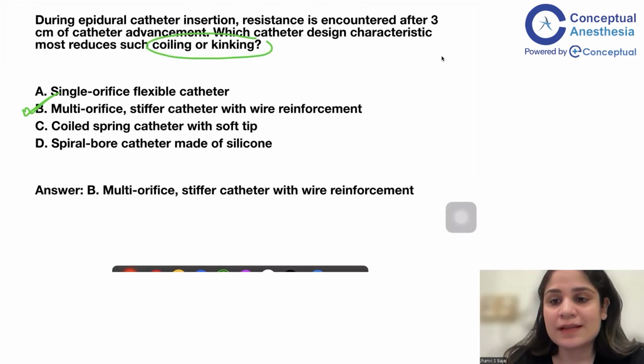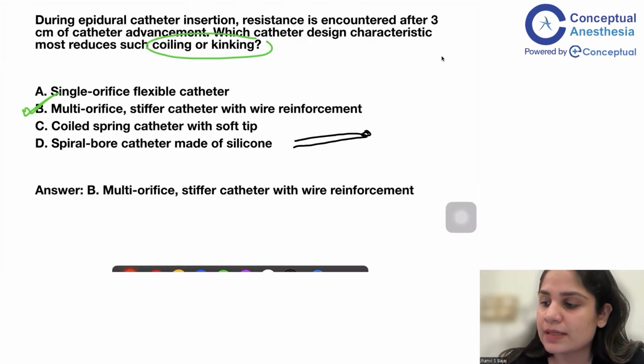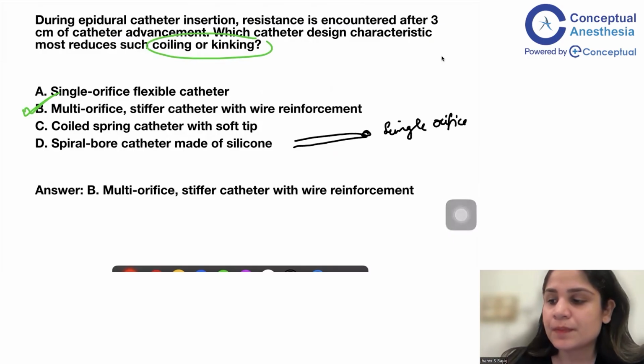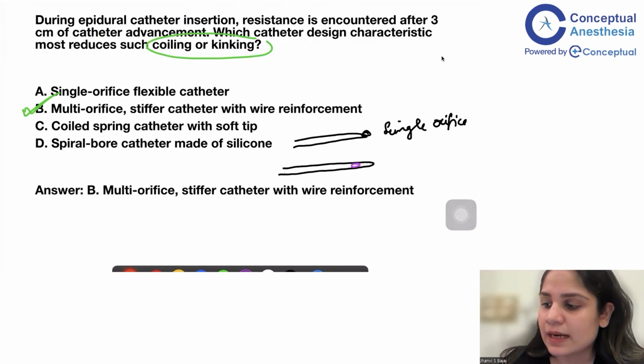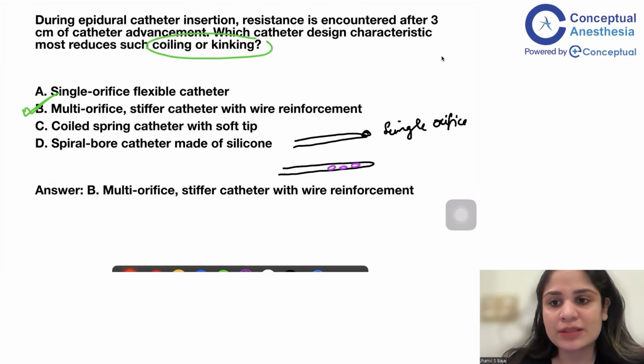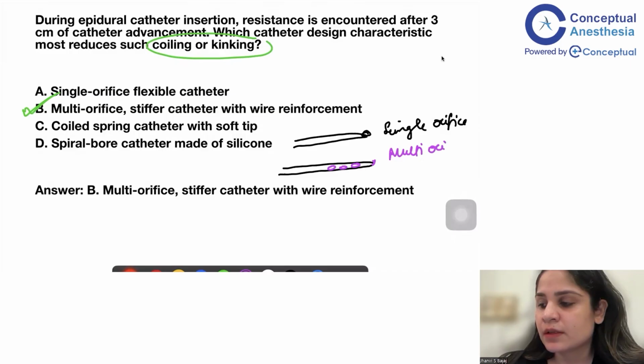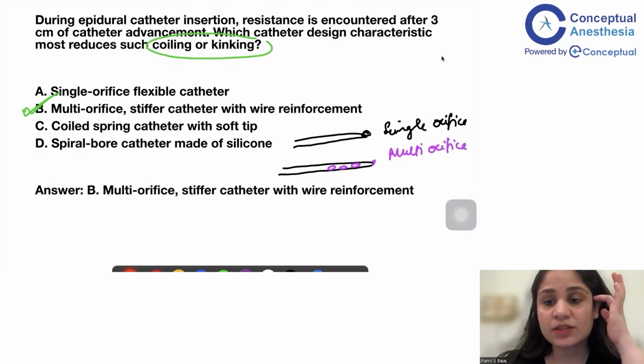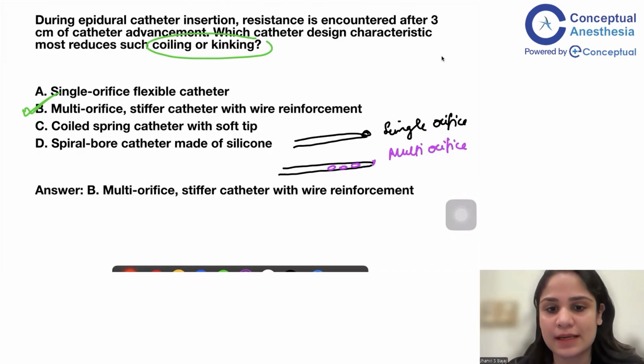Now, what is a multi-orifice and a single orifice catheter? Okay, so now if you see an epidural catheter that on its tip has an opening, only one single opening, we will call this a single orifice epidural catheter. But if you see another catheter, the tip is blind, that means the tip is closed, and on the side you have these openings. Typically, we have about 3 openings on the side at 0.5, 1 and 1.5 centimeter from the tip. Okay, so this is called as a multi-orifice catheter. It is seen that multi-orifice catheters help in distribution of the drug much better as compared to single orifice catheter. So what we prefer nowadays in the epidural space is the multi-orifice stiff catheters with wire reinforcement.